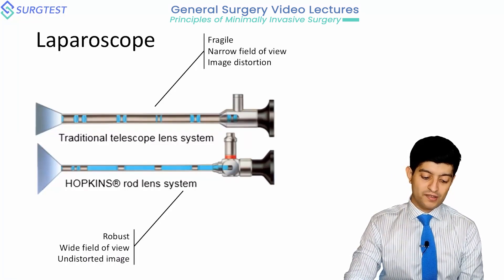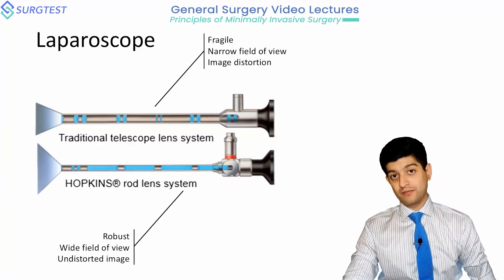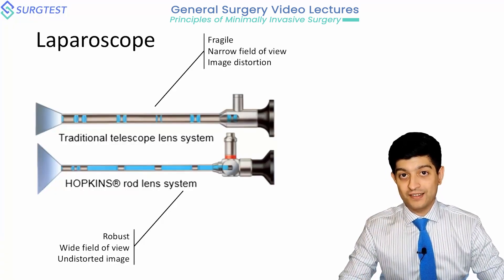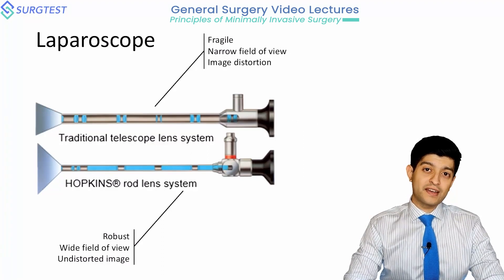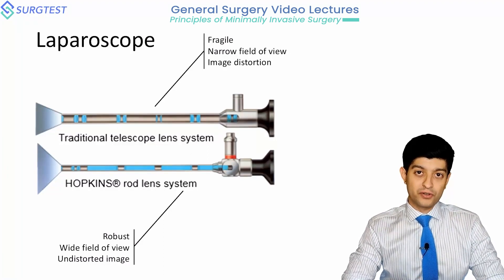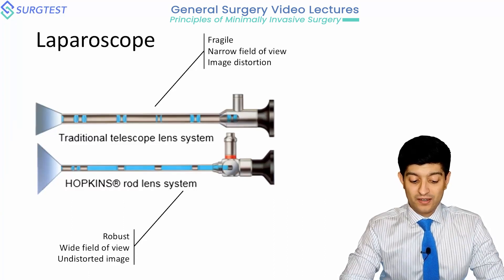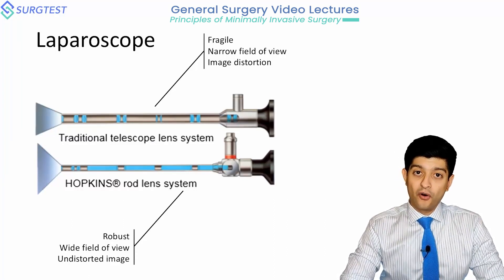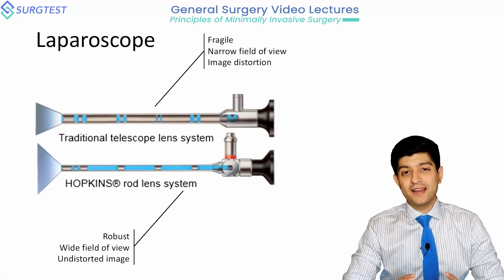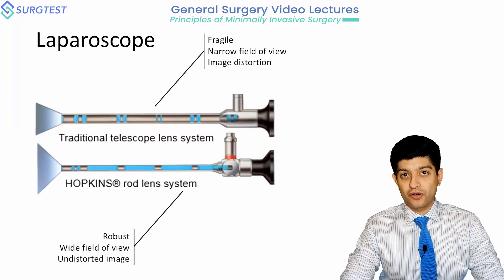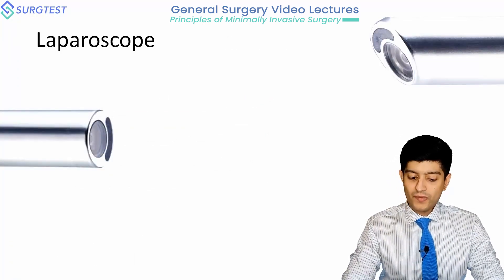The advantages of the Hopkins system are that it is relatively robust — though these are still sensitive instruments — and it offers an extremely wide field of view. As you can see in the diagram, it's much wider than the traditional telescope lens system. Because the cylinders are so long, there is also a lesser likelihood of seeing a distorted image due to production inconsistencies.